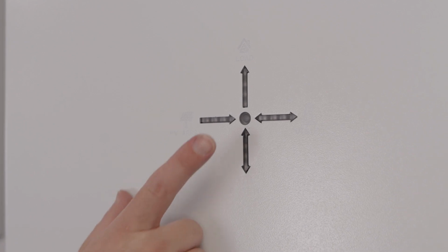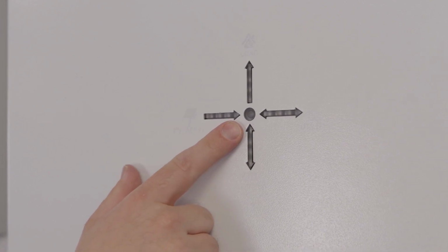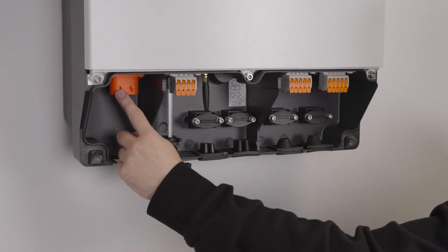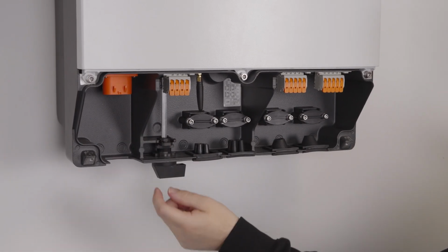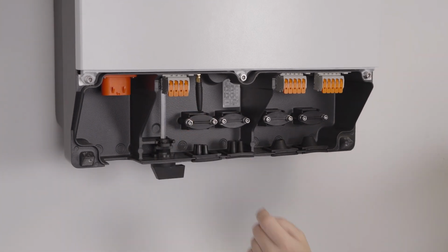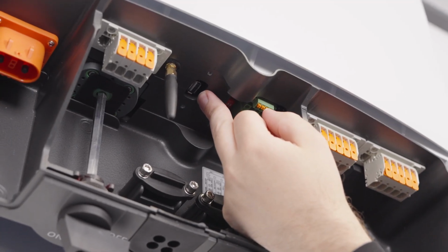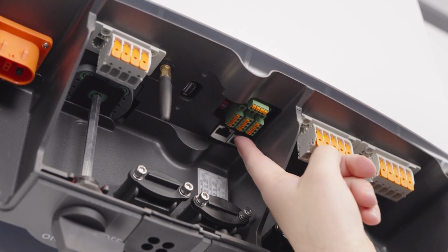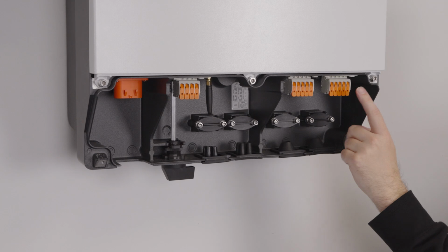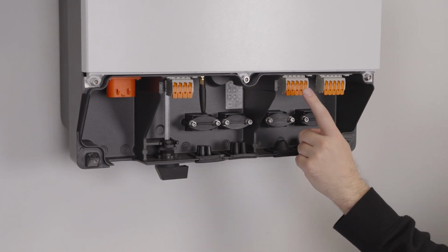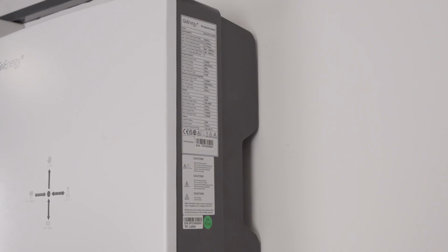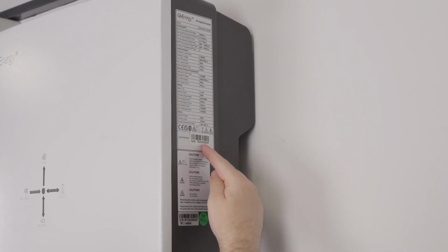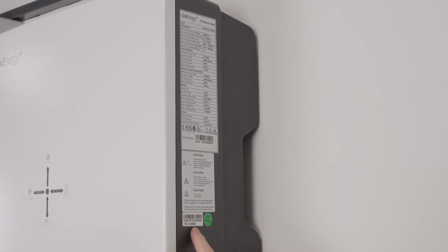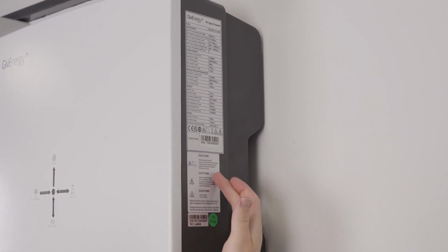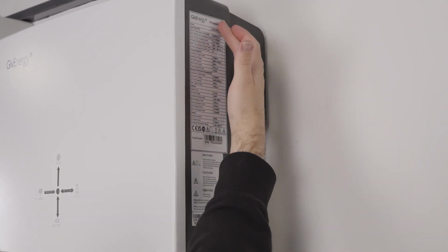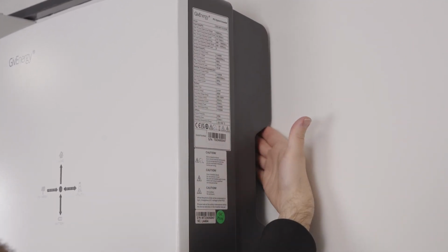Step 2. Familiarise yourself with the inverter. The 3-phase Gen 3 inverter has a power flow direction indicator here and a battery connection point here. The PV input switch is here and the PV input terminals are here. The USB port is here and the communication ports are here. Here is the AC supply terminal on the right and the EPS terminal is here on the left. Here you will find the serial number of the inverter and the Wi-Fi serial number with verification code. Here is the warning signs label, and here is the specifications label. And here is the heatsink.